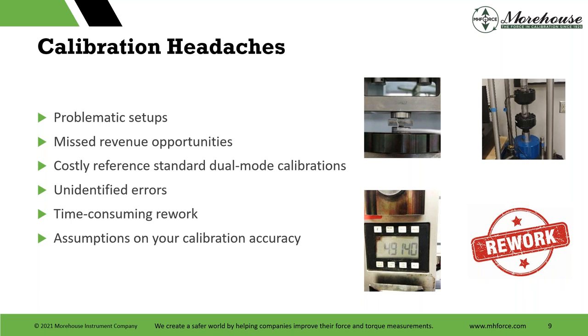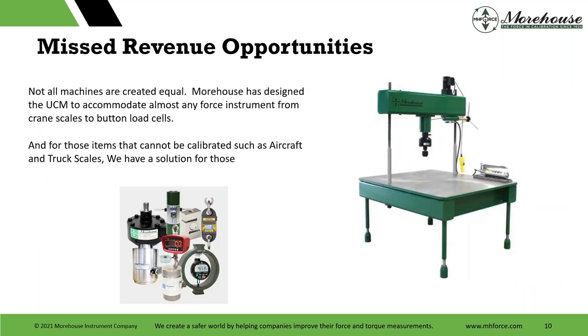go back to the ISO 376, where the recommendation is to have different adapters for compression and tension, because usually load cells or the instruments have different setups and adapters. Other headaches: unidentified errors, time-consuming rework, and assumptions on your calibration accuracy and uncertainty. Hopefully that guidance document, which we'll share later, will take away a lot of those assumptions. And then not all machines are created equal. We designed our UCM to accommodate almost any force instrument, from crane scales to button load cells. And for those that cannot be calibrated, such as aircraft and truck scales, we have a solution. That's our USC 60K machine.